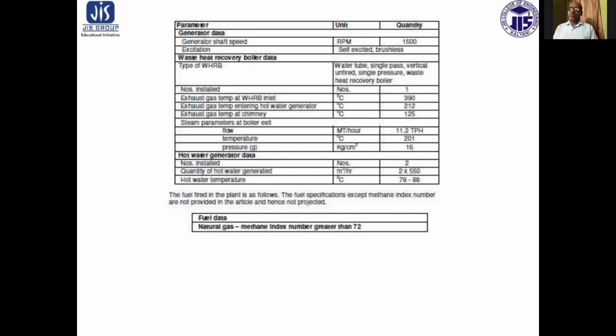Waste heat recovery boiler data, that is water tube single pass vertically unfired single pressure waste heat recovery. Exhaust gas temperature inlet 390 degrees centigrade, and exhaust gas temperature entering hot water generator 212 degrees centigrade. Exhaust gas temperature at chimney 125 degrees centigrade.